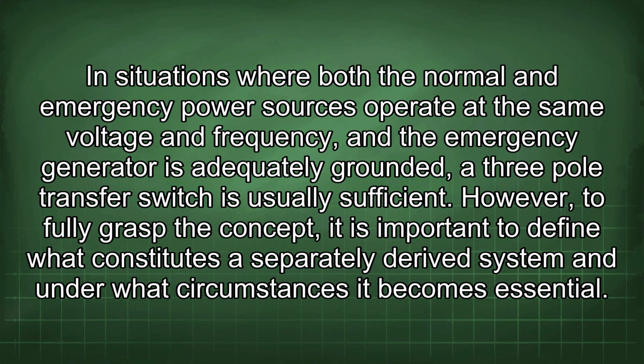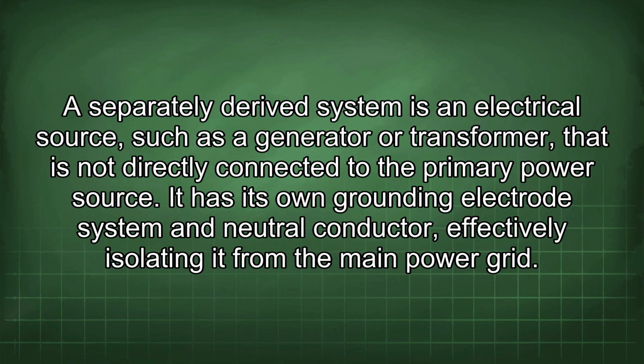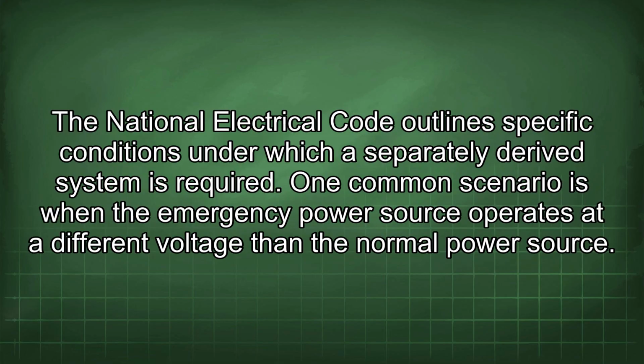However, to fully grasp the concept, it is important to define what constitutes a separately derived system and under what circumstances it becomes essential. A separately derived system is an electrical source, such as a generator or transformer, that is not directly connected to the primary power source. It has its own grounding electrode system and neutral conductor, effectively isolating it from the main power grid. The National Electrical Code outlines specific conditions under which a separately derived system is required.